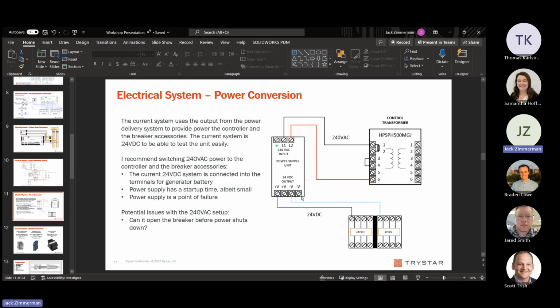And also, this is the biggest reason: having a power supply power the breaker accessories. We spec a $350 power supply. It's a top of the line one. I mean, it's made for this kind of stuff, but power supplies, I think, are too risky to be a single point of failure for turning the controller off. Even the nicest ones, switching power supplies, we use them in a lot of stuff, but for this kind of thing, I'd rather just run straight voltage to it.